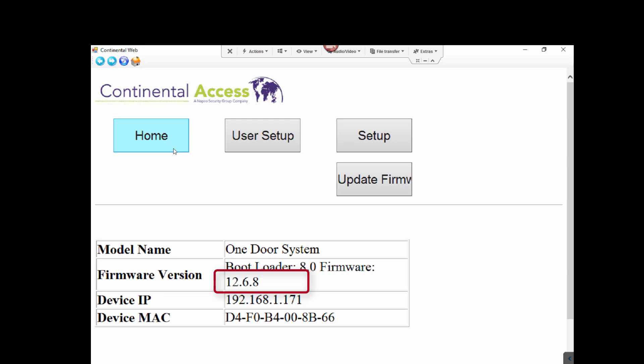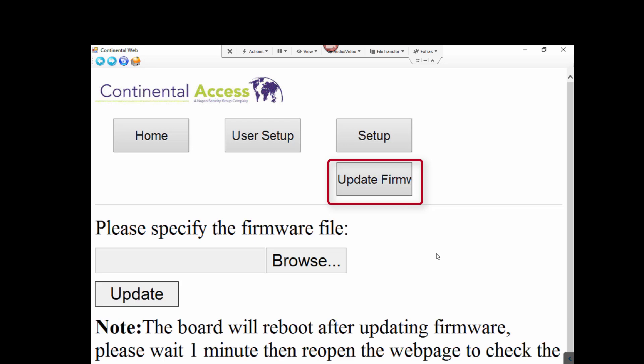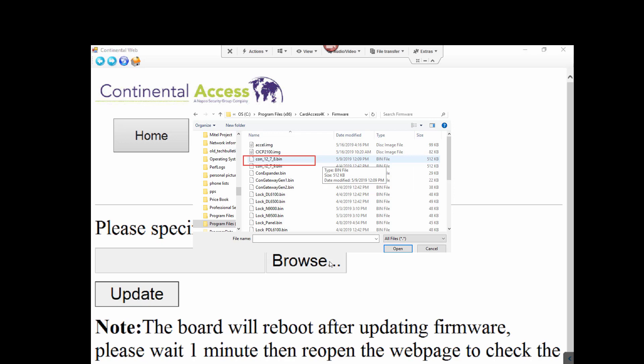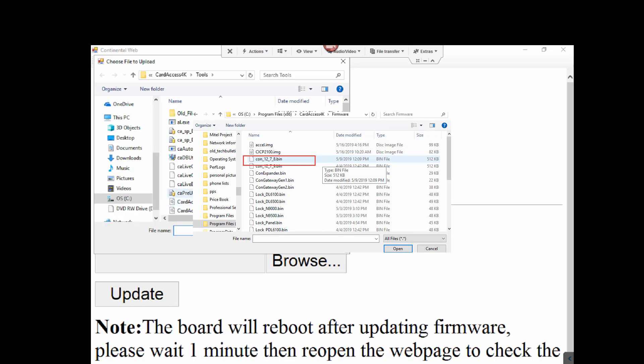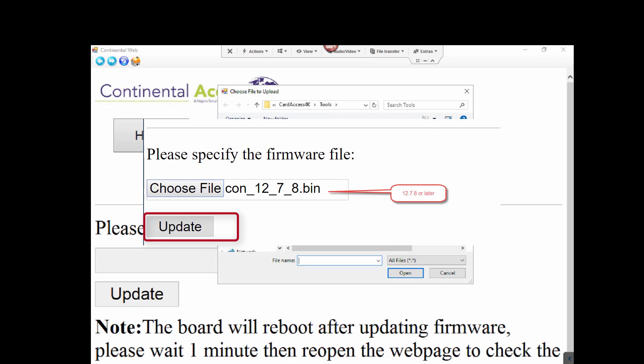If the firmware is not 12.7.8 or later, you need to update the firmware. To update the Ethernet firmware, click the Update Firmware button, then click the Browse button. Navigate to the Firmware folder and select the CON_12.7.8 or later .bin file. Once the file is selected, click Update. The board will reboot after updating the firmware.